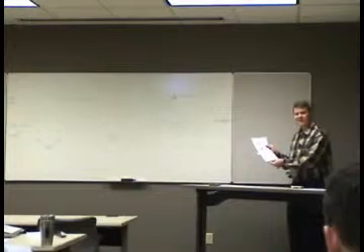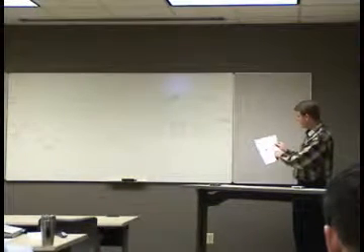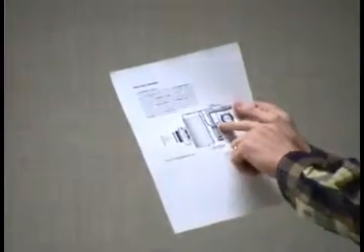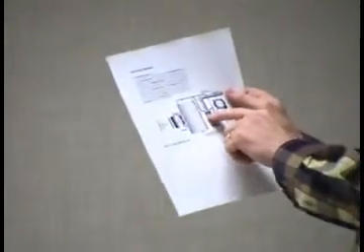on the first, which was first? I think the first one they showed as the cooling refrigeration cycle. You see coming out of the bottom of the compressor, a skinny little line goes into the three-way valve, comes out of that bottom port, and goes through a water to refrig heat exchanger. This was a nice Trane diagram that I pilfered off the internet. They're showing a water coil and an air coil for the indoor coil. But we got that discharge of the compressor going through the water coil, which we got, well water, cooling tower water going through it to cool it off.